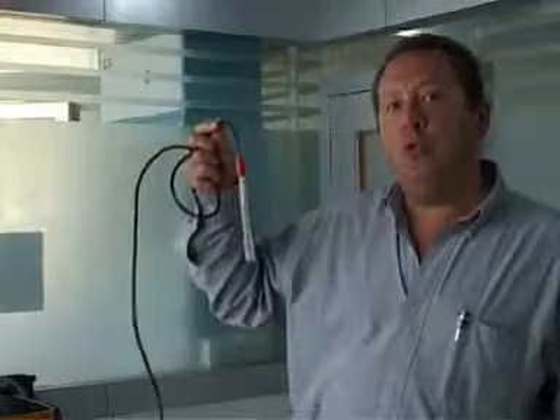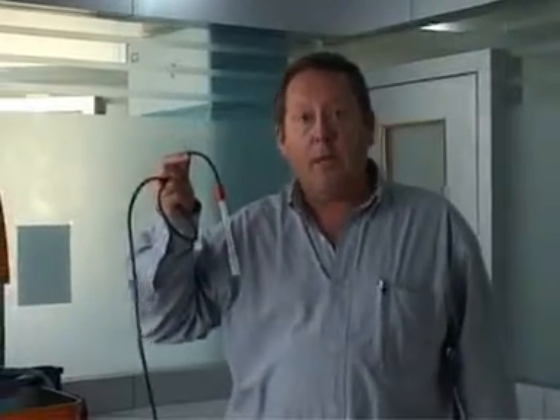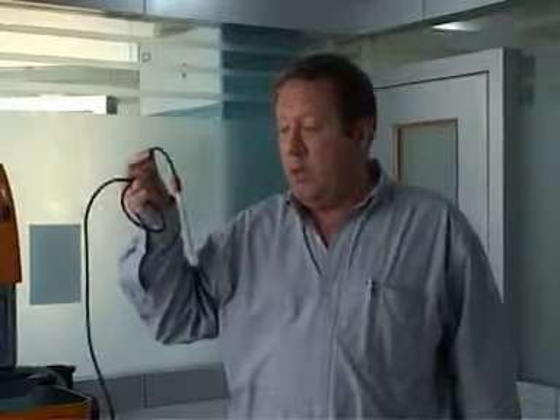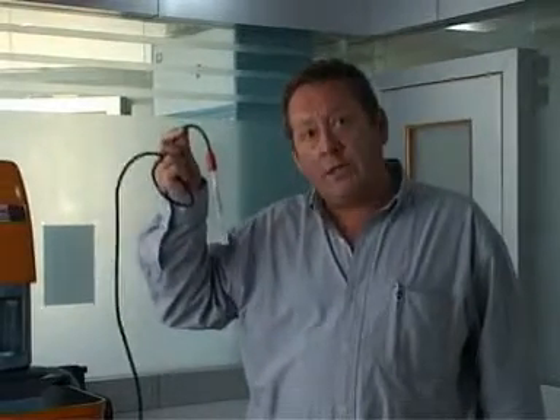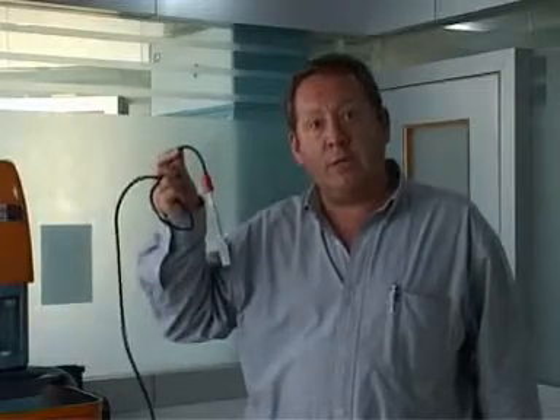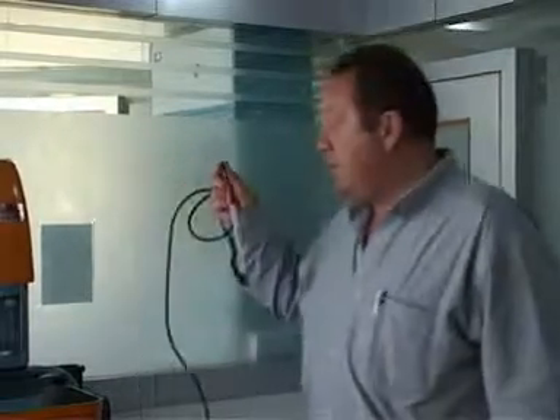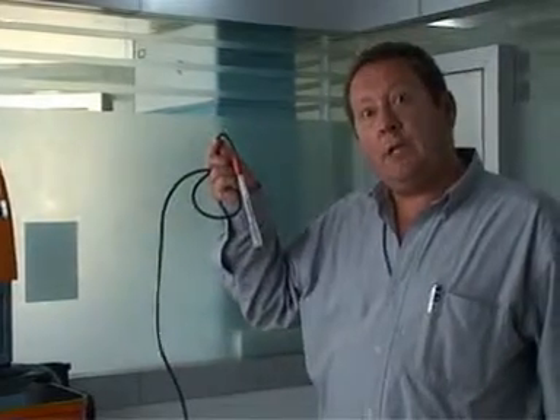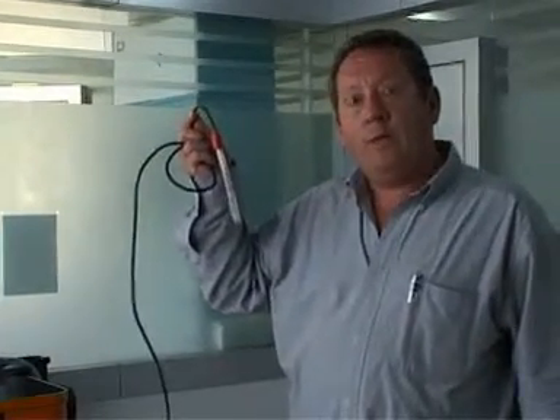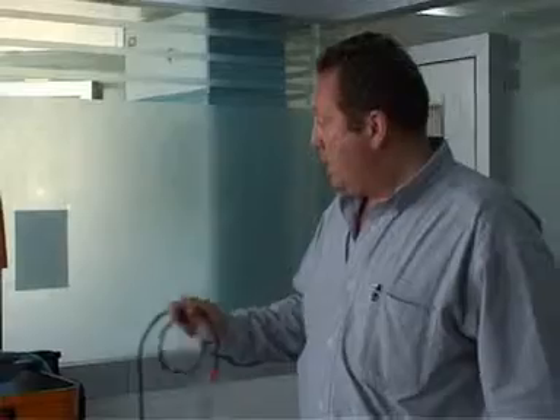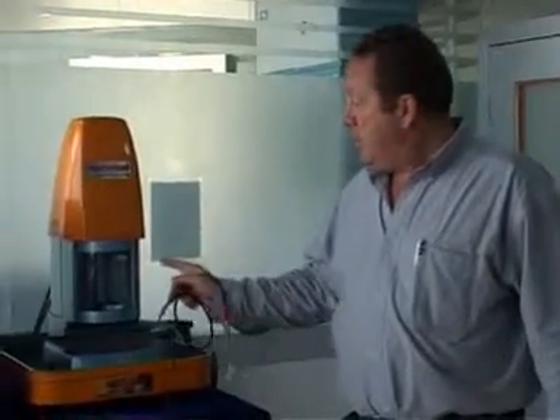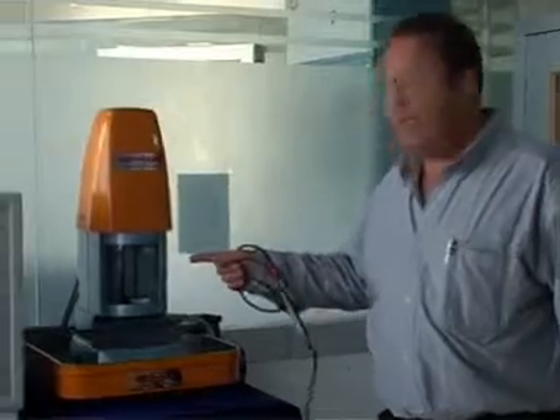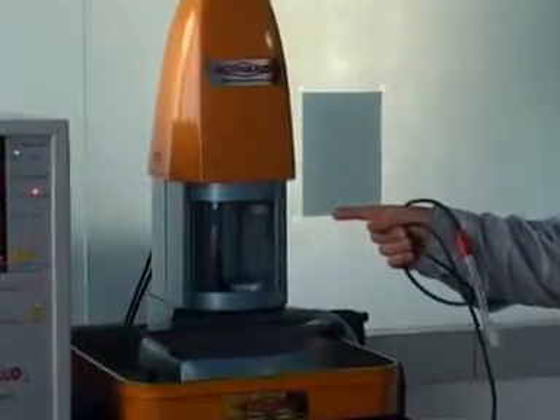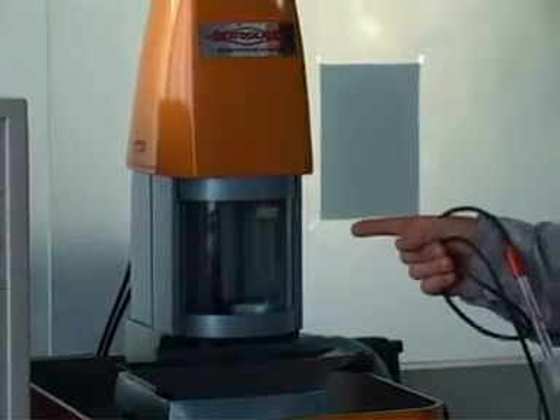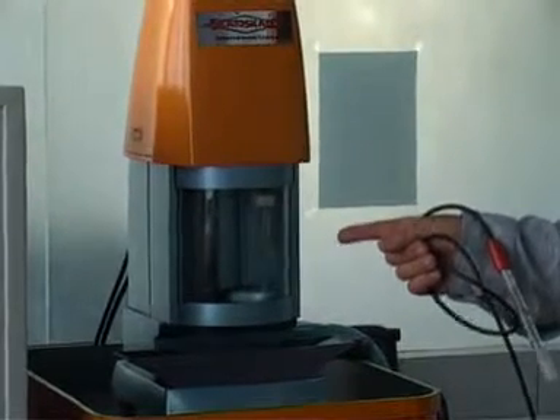Also, the method used for cleaning the probe is mechanical cleaning. Mechanical cleaning runs the risk of damaging a glass probe. So you have no means of calibrating the correct pH reading, and you do not know over the entire period of the shift if the measurement is correct. This system has 2 probes and is regularly cleaning the probe to ensure full calibration and an accurately cleaned probe.